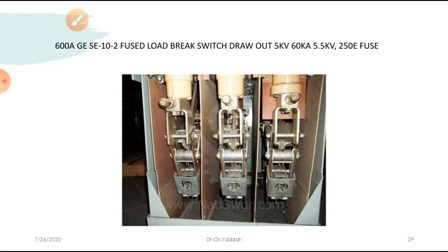Now, it is exposed to mechanical, thermal and dielectric stresses during the switching operation, because we do the work in a small chamber. Then automatically whenever the circuit is opened or closed, high stresses develop. What are the stresses? It may be mechanical, thermal, or dielectric stresses raised during this operation. These stresses should be withstood by the body which you make for the air break switch. Generally these air break switches' operating voltages are nearly from 12 kV to 36 kV. That is medium voltage only.